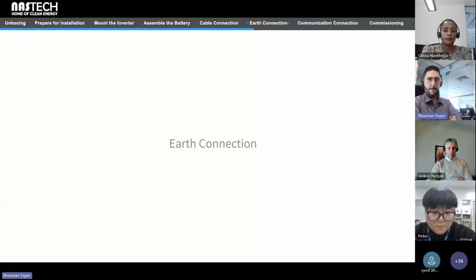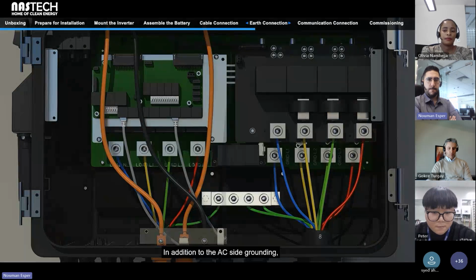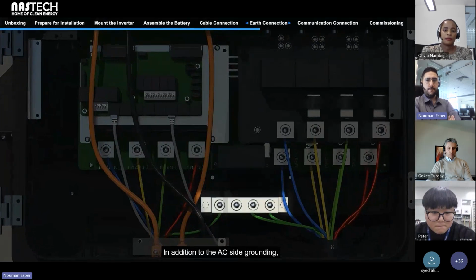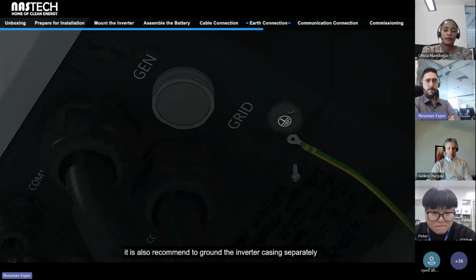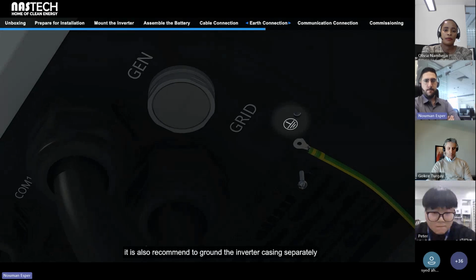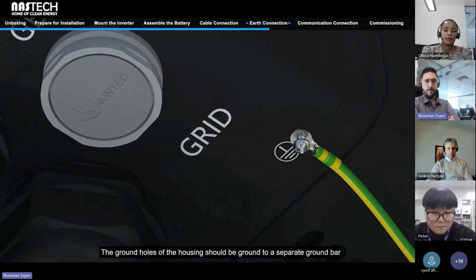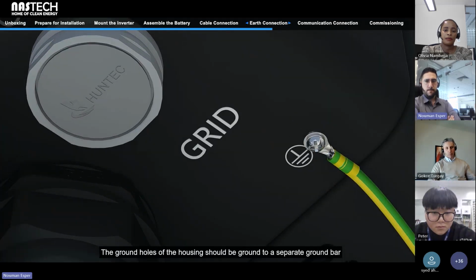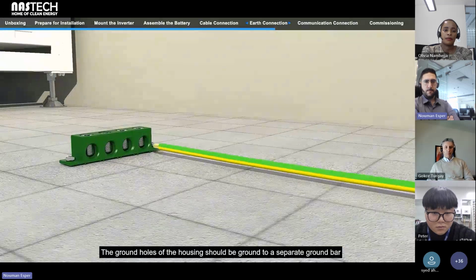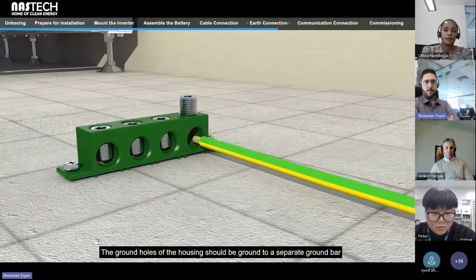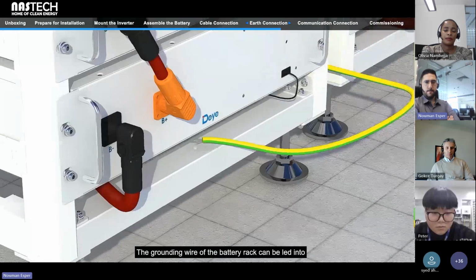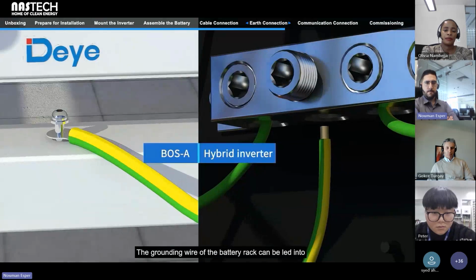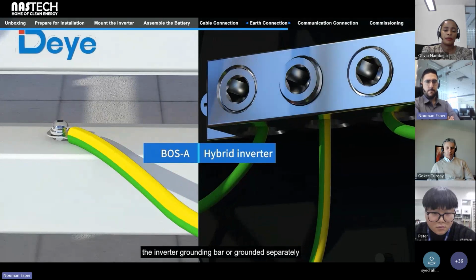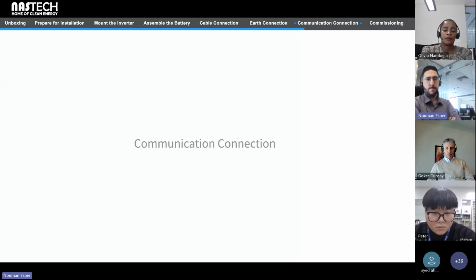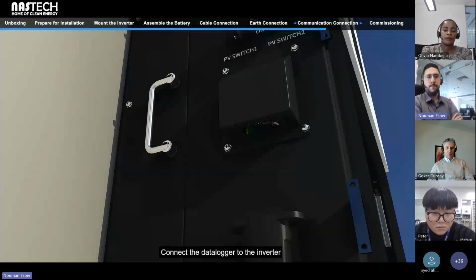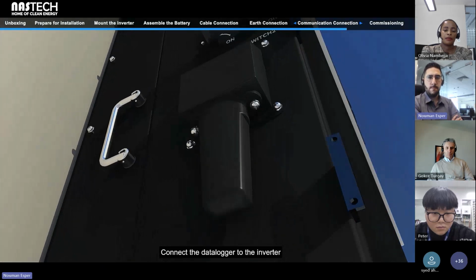Earth connection. In addition to the AC side grounding, it is also recommended to ground the inverter casing separately. The ground holes of the housing should be grounded to a separate ground bar. The grounding wire of the battery rack can be led into the inverter grounding bar or grounded separately. Communication connection. Connect the data logger to the inverter.